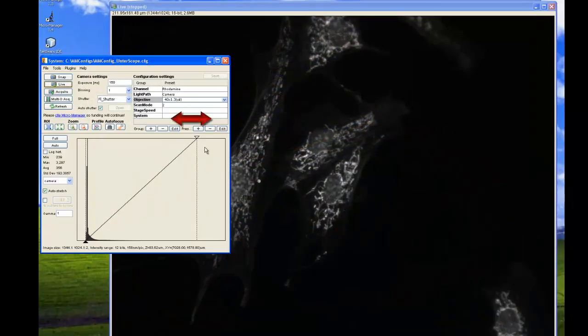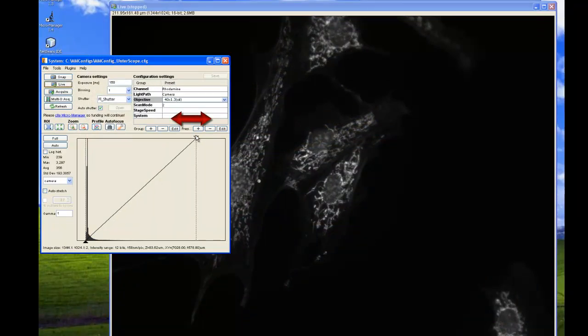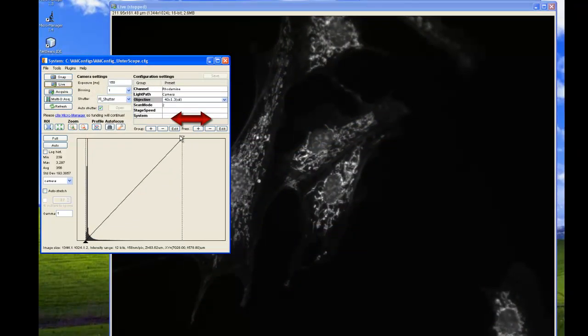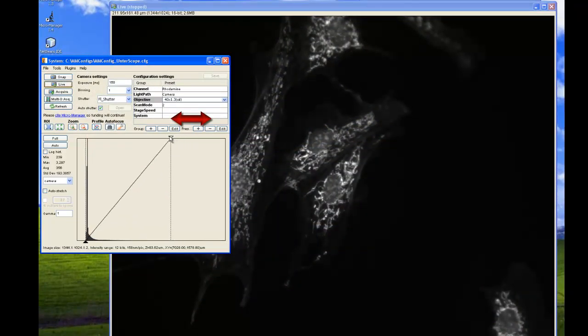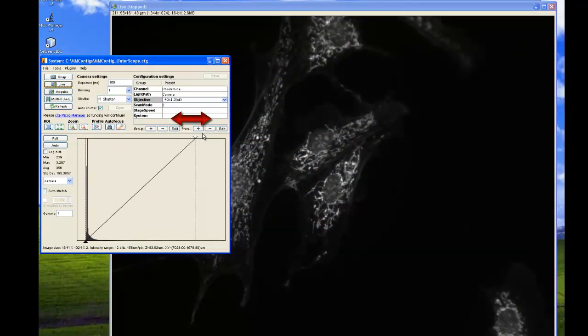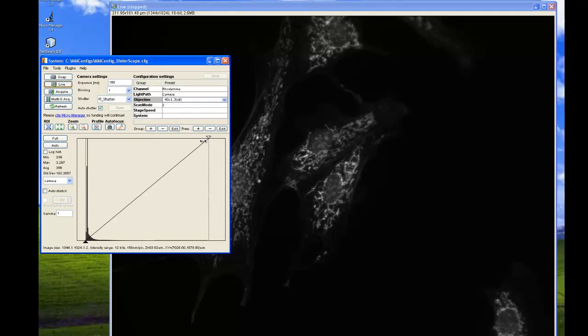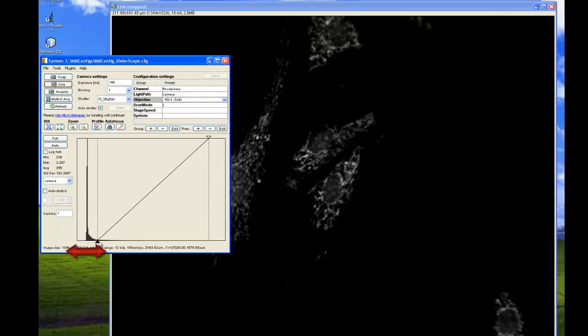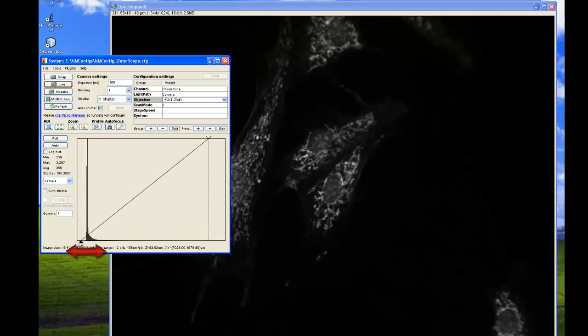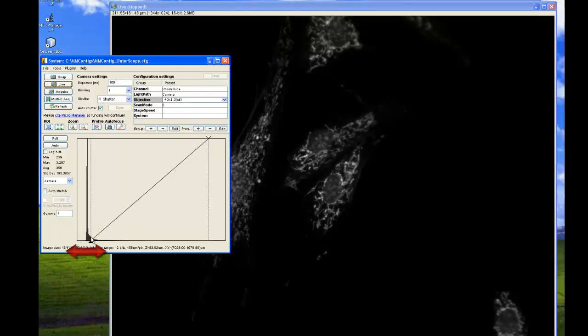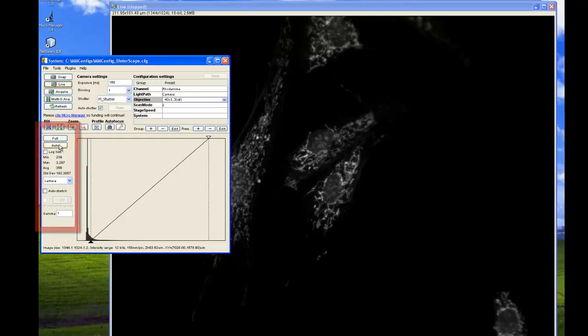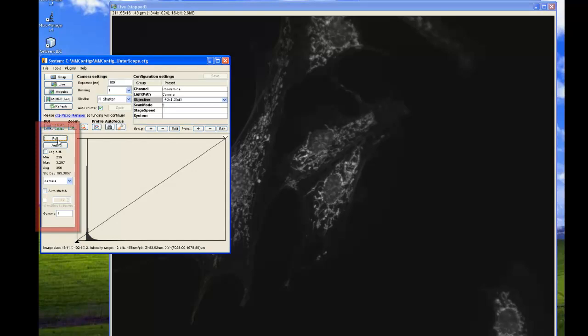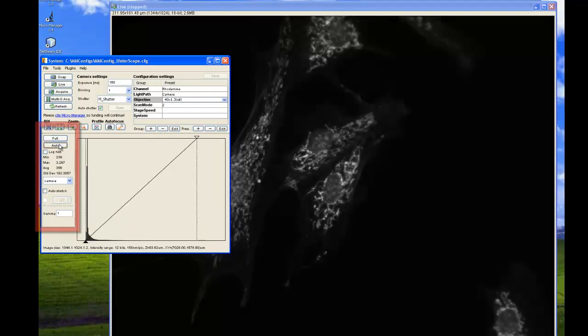You can adjust the brightness and contrast of your image in the interactive histogram display by moving the black and white arrows at the endpoints of the graph. This sets the upper and lower clipping levels. Basically, what this means is that the pixel values lower than the black triangle will appear black, and the pixel values higher than the white triangle will appear as white. On the left of the histogram, you can select Full to set the upper and lower clipping levels of your camera's full intensity range. Or, select Auto to set it based on the extreme pixel values in the image.